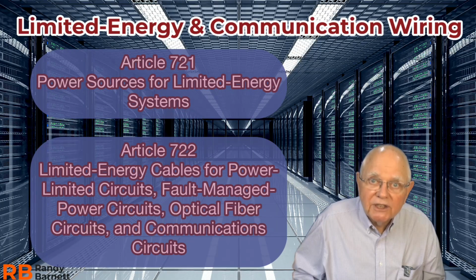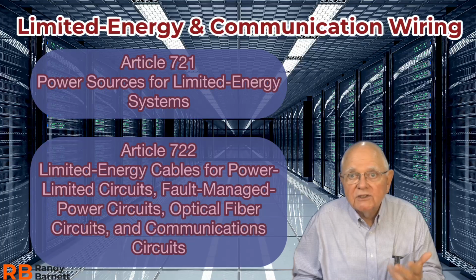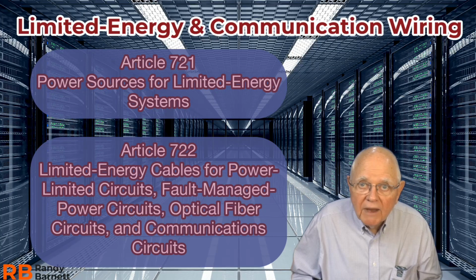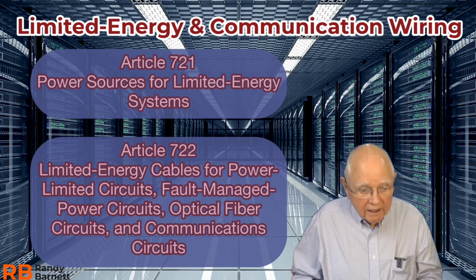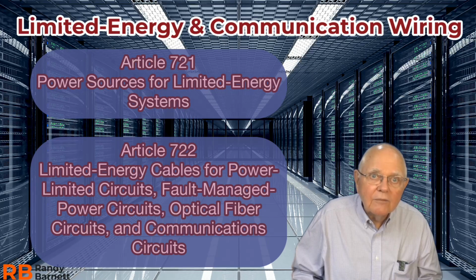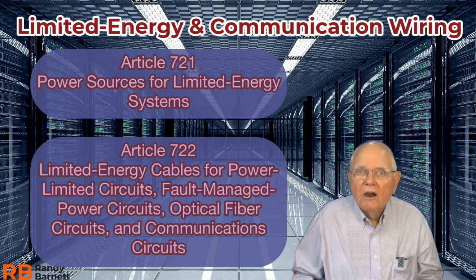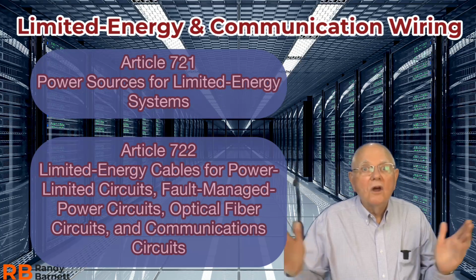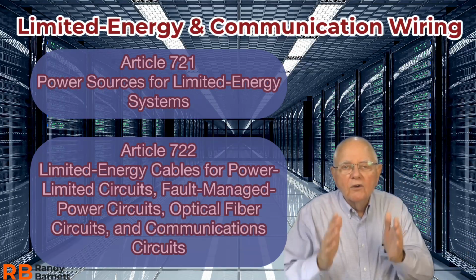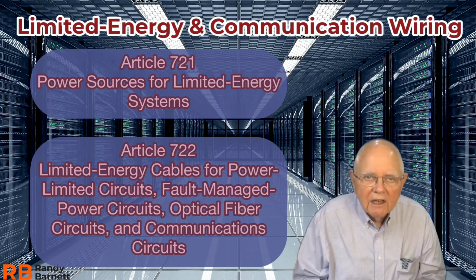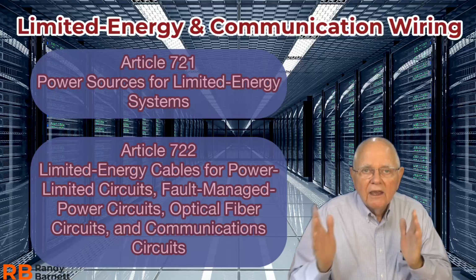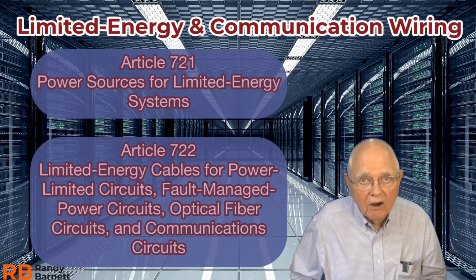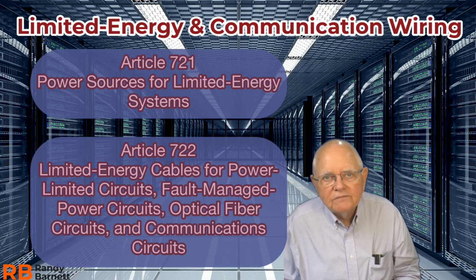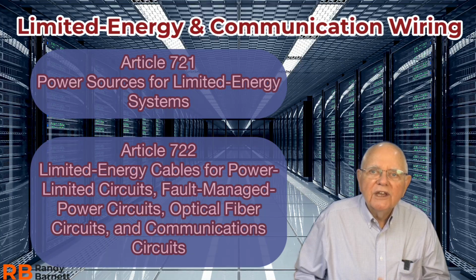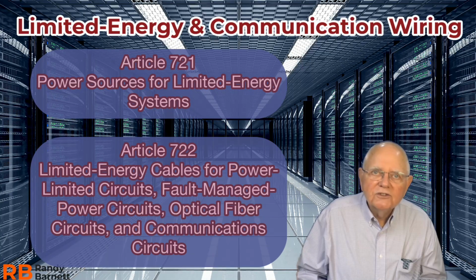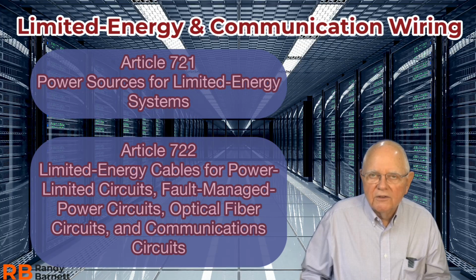Our limited energy cables for Class 2, Class 3, and Class 4 power sources. And it covers optical fiber cable, fiber. That used to be Article 770. We had a whole Article 770 devoted to optical fiber systems. That has been deleted now, and now that information is in Article 722. And then we have communication circuit cables, also covered in Article 722.